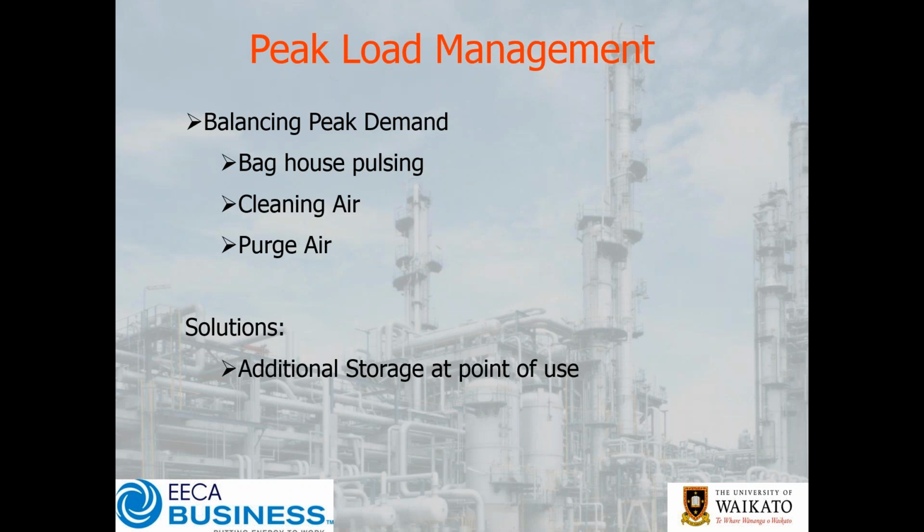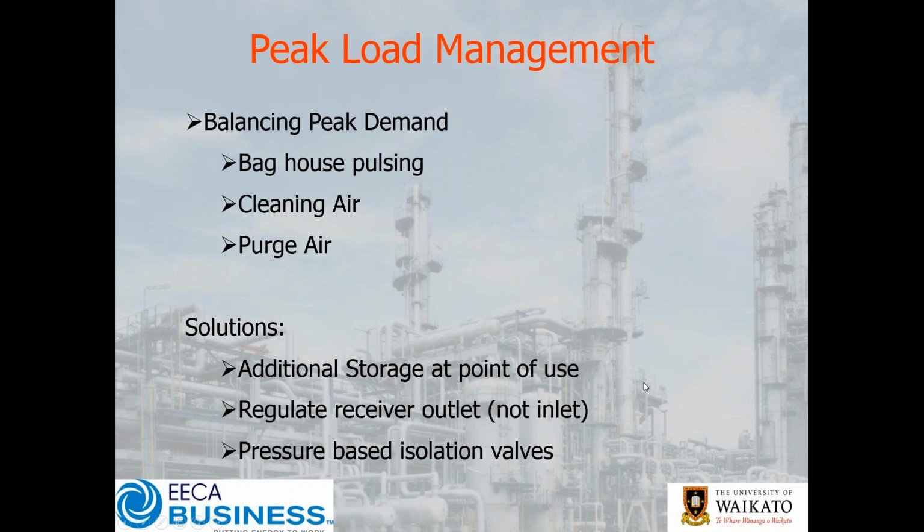Now, you might not be able to do that if it's a safety risk to have the baghouse stop pulsing, but there are things that you can put in place, mitigation factors to think about. So obviously regulating your receiver outlet, not the inlet. You want your storage to be at the highest pressure possible. And the pressure-based isolation valves that we just sort of talked about. So there's a number of things you can look at to do this.